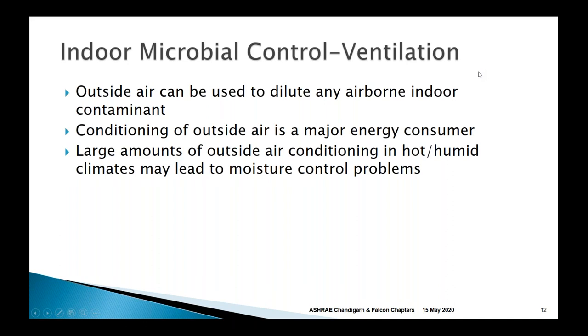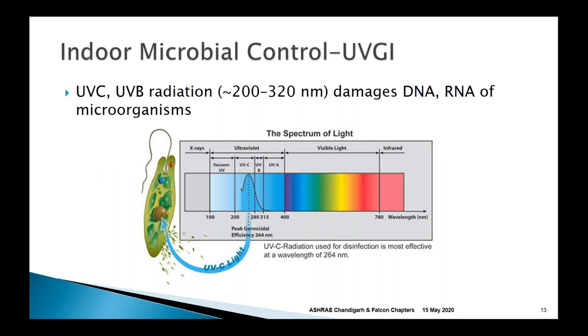Ventilation will dilute all airborne contaminants, but depending on the climate it can be a very expensive energy proposition — particularly in hot, humid climates. UVGI is a technology that inactivates microorganisms rather than removing or displacing them. It uses mainly ultraviolet C and ultraviolet B radiation in the 200–320 nanometer spectral range, which damages the DNA and RNA of viruses, bacteria, and fungi.